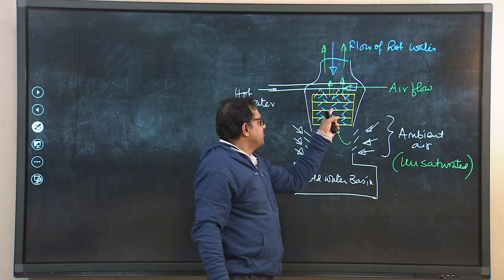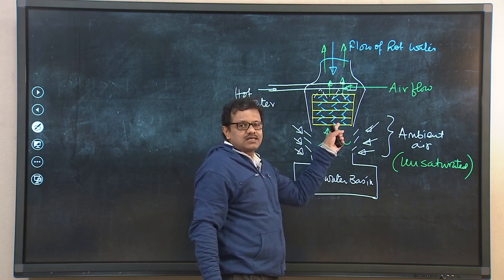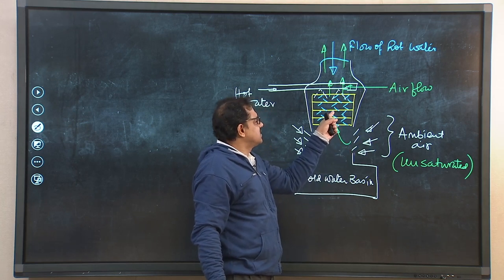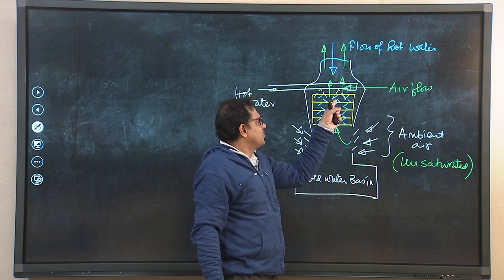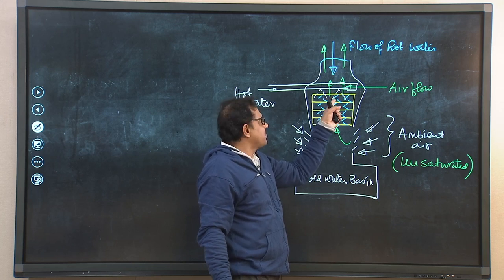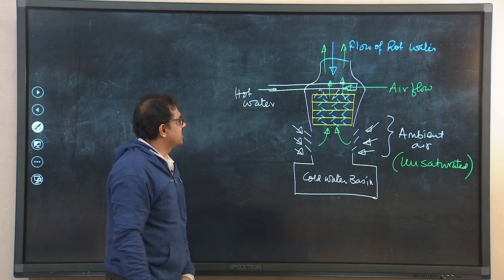If the incoming air gets saturated midway in its travel upward, that saturated air will again be in contact with hot water towards the upper part of the fill, and eventually we get hot and moist air exiting the tower. The water can be cooled due to evaporative cooling only up to a temperature that is the wet bulb temperature of the incoming ambient air, because if air becomes saturated no further cooling occurs due to evaporation.